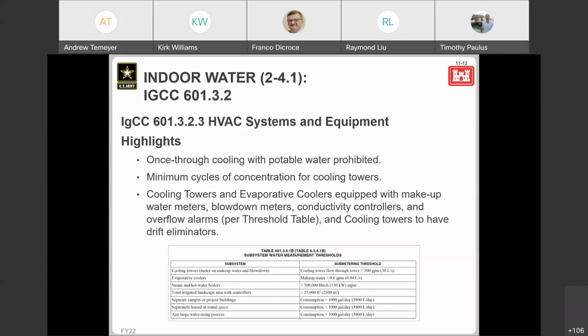Some of them are real world things, so that way you can see how your system's actually performing. If you have meters, you can track how much is coming in and going out. Controllers for the conductivity, your water quality, and an alarm, so that if a valve is stuck open and you're just overflowing and sending things to the drain. And then drift eliminators, which are an easy way to keep the water in the tower. It sounds pretty simple, but these are just real world applications. Hopefully people that are doing the cooling tower design or evaporative cooler design are familiar with these things and putting them in the projects, and nothing too crazy with all that.